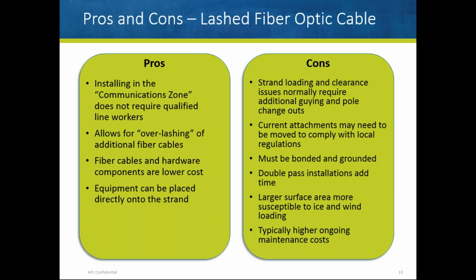Some of the negatives of lashed fiber really start with loading. The messenger wire is a pretty heavy load onto any existing structure, and installing in the communication zone can lead to significant clearance issues. That loading can require additional guying, especially on angled structures, and potentially pole changeouts for the loading issues.